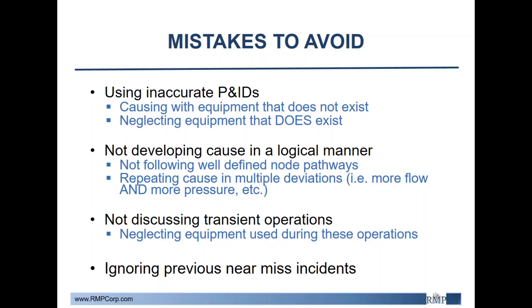Next would be not developing causes in a logical manner. This could involve not properly highlighting the node on the P&IDs or not following the process pathway well when discussing causes. This could lead to either missing information or, in contrast, repeating information. Repeating causes across multiple deviations can lead to inconsistencies within the study and is also a waste of the team's time.